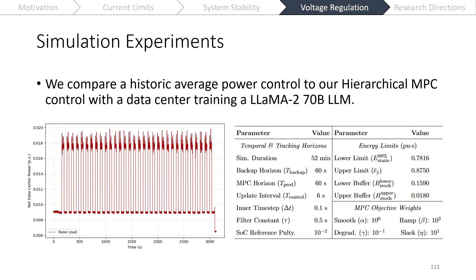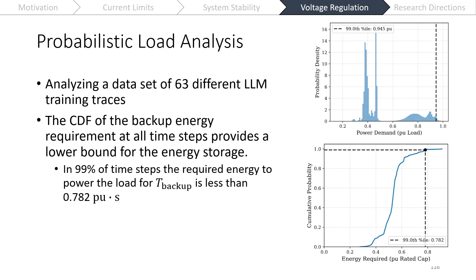For the droop proportional controller that we have here, to try to find a lower limit on how far we can dispatch that storage, we look over lots of different test data sets. We've looked over 63 different large language model training traces that we build up to be what the load would be for our data center. And then we can find the point that at least 99% of the required backup energy storage would fall below. We use this as the lower limit for our droop controller to get more of a fair comparison. This value also provides an upper limit on that lower limit that we're predicting, which makes it nice to have a little bit less when our buffer goes beyond that point.